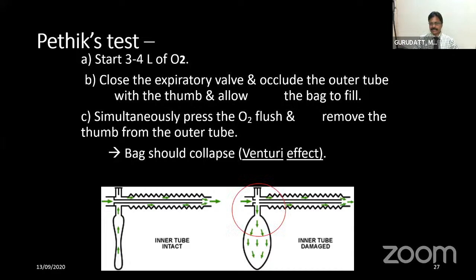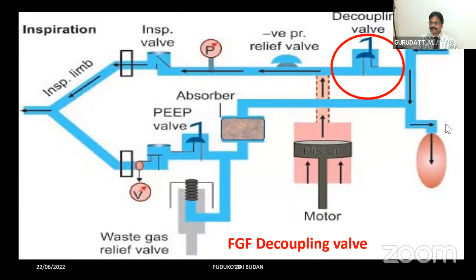What we have is the decoupling valve. Because of the presence of this decoupling valve, the fresh gas flow during inspiration cannot directly enter the inspiratory limb of the circle system. Here you can see that in Draeger machines the ventilator is a piston driven ventilator. Here, this is the inspiration. The positive pressure is created in the inspiratory limb, and because the positive pressure is created, the decoupling valve, which separates the fresh gas flow from the inspiratory limb, is closed. Because it is closed, all the fresh gases enter into the bag. So even if you activate the flush, all the gases enter into the bag, and barotrauma is prevented because the fresh gases cannot directly enter the inspiratory limb during inspiration in a Draeger machine.